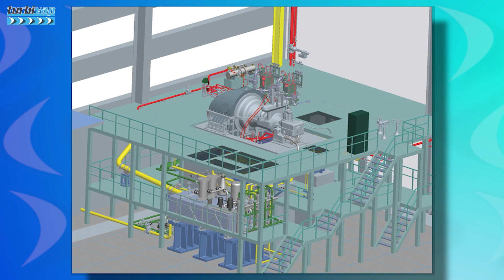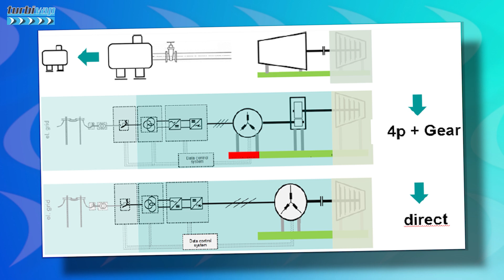Then there's the removal of the steam or gas pipes and the installation of the high voltage infrastructure. These must be completed in short maintenance windows, requiring coordination between experts, manufacturers, and operators. Uncoupled and coupled, they will check vibrations and temperature, while torsional analyses can ensure that electrical excitations, like short circuits, do not compromise the system.